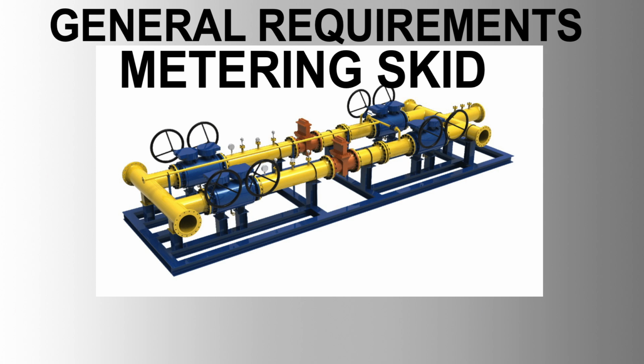Turbine meters, 0.25% of reading. Ultrasonic meters, 0.15% of reading. Coriolis meters, 0.1% of reading. Repeatability, better than 0.03%. Drift, 0.015% of reading per year. Materials, wetted parts should be stainless steel, unless otherwise specified for specific fluid process conditions.